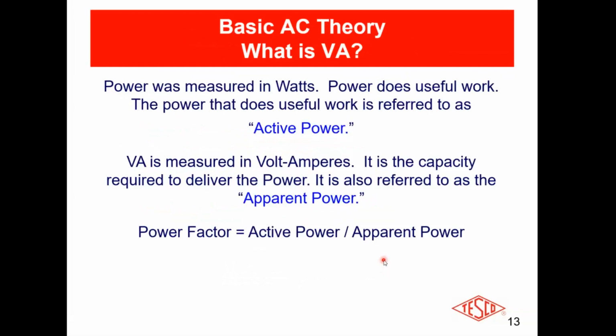All right? Now, one of the really important things in our industry is active power and apparent power. Your power factor is nothing more than the ratio of those two: active power divided by apparent power. What the heck is the difference? We bill our customers based on active power. What we deliver to our customers is apparent power. So if your power factor is 1, what you are delivering and what you're getting paid for are exactly the same.